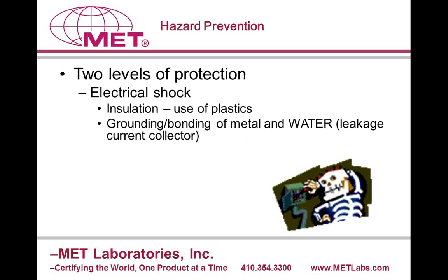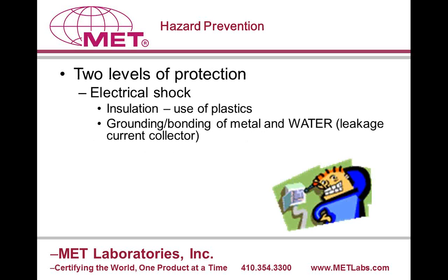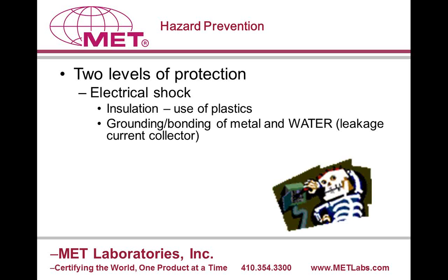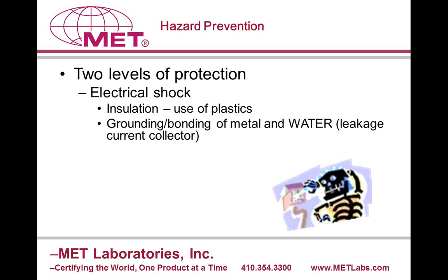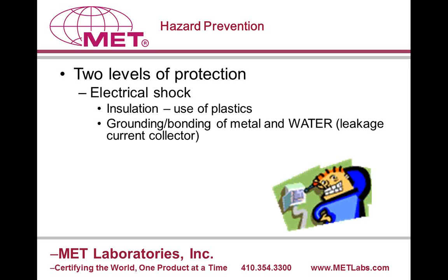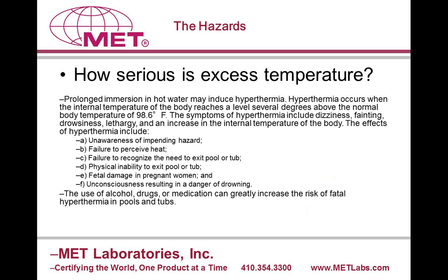So when designing to protect against electric shock, you should be covering or surrounding all live parts with insulation, such as wire insulation, terminal blocks, and enclosures. If an enclosure is made of metal or has metal parts that could touch a live part, they also need to be electrically bonded together and tied to ground. You will also need to pass all water through a bonded metal leakage current collector. We'll talk more about this later.